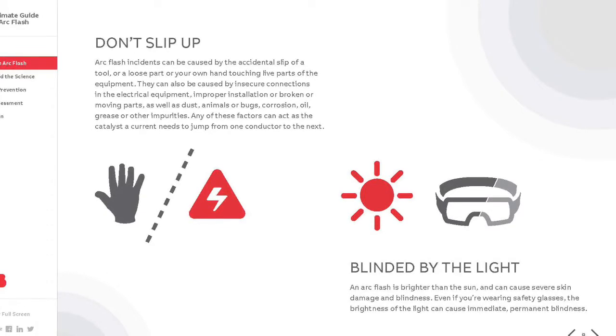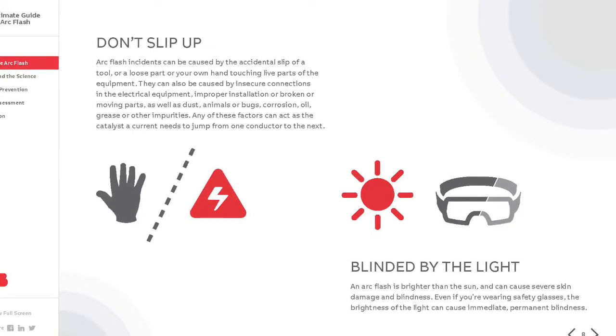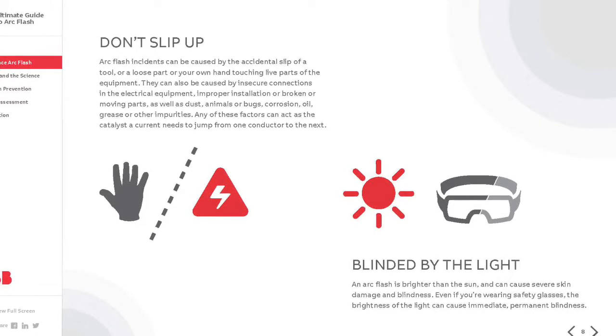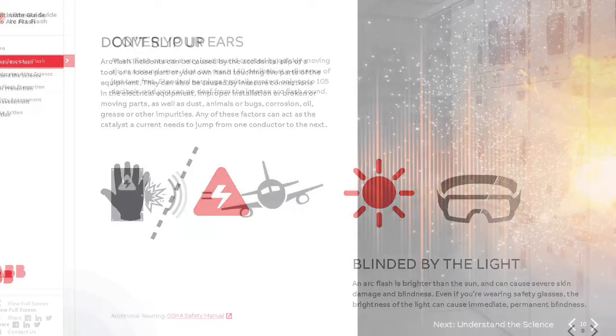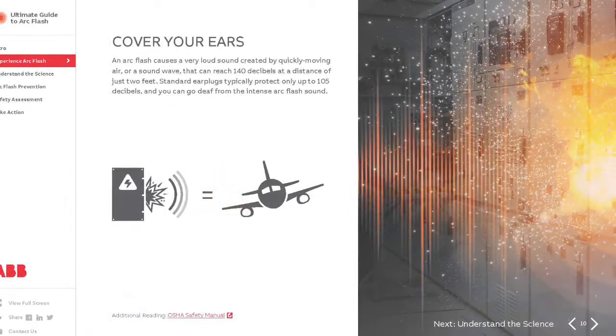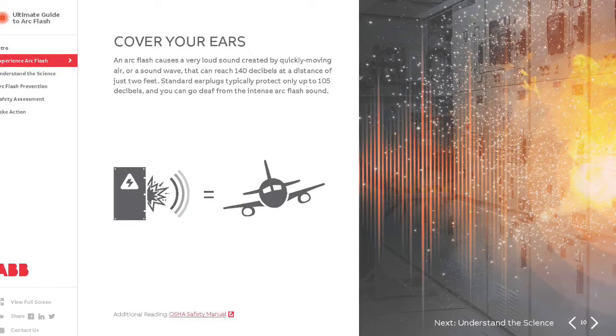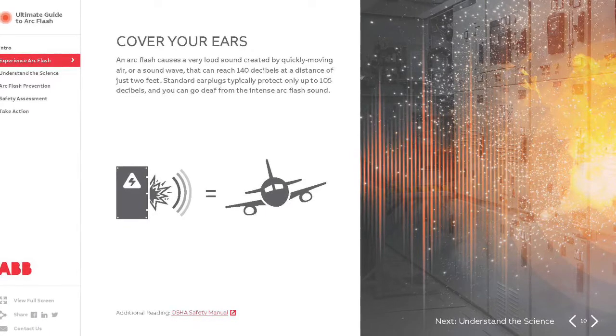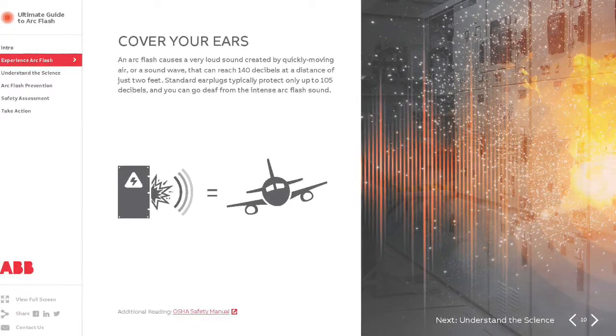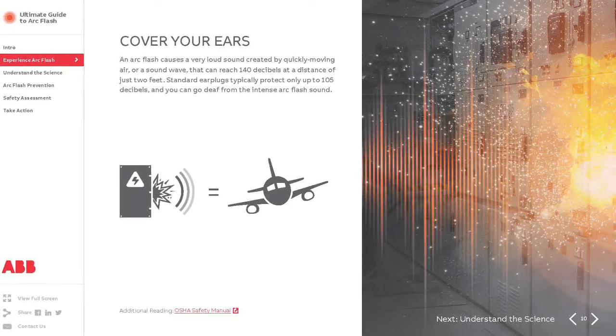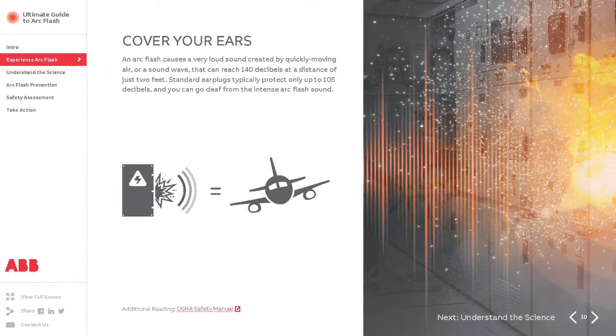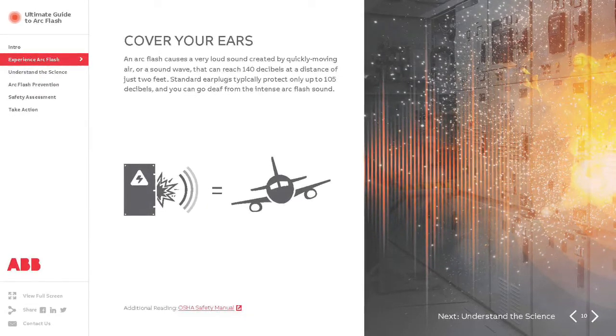An arc flash is brighter than the sun and can cause severe skin damage and blindness. Even if you are wearing safety glasses, the brightness of the light can cause immediate permanent blindness. An arc flash causes a very loud sound by quickly moving air — a sound wave that can reach 140 decibels at a distance of just 2 feet. Standard earplugs typically protect only up to 105 decibels, and you can go deaf from the intense arc flash sound.